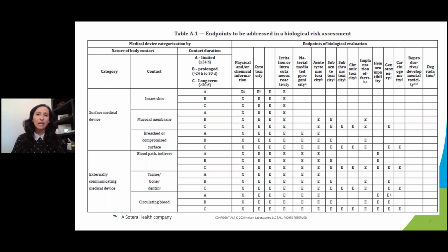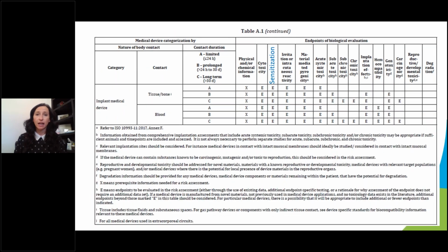So this is how we want to think about biocompatibility. We talk first about our category and then contact. So is it a surface device? Is it contacting skin, or is it going to be internal with the circulating blood? We also have implants. There's a second half to this chart. And then we talk about the contact duration: less than 24 hours, 1 day to 30 days, and then greater than 30 days. And then you'll see that there are marks in each of these endpoints. So we've kind of taken the human body and broken it up into endpoints that we can evaluate, and we've marked them with an X or an E. And I just want to highlight here, this is the second half of the table.